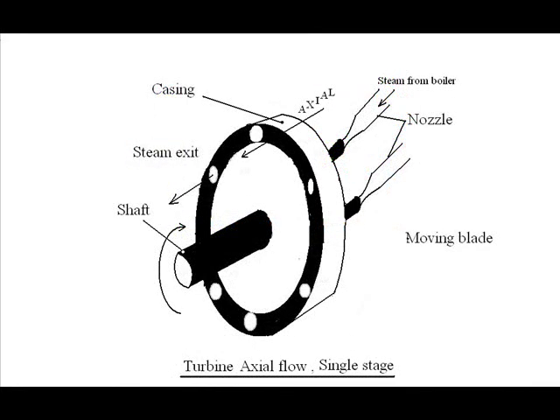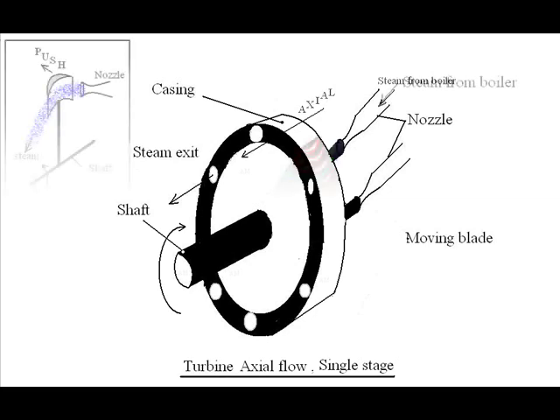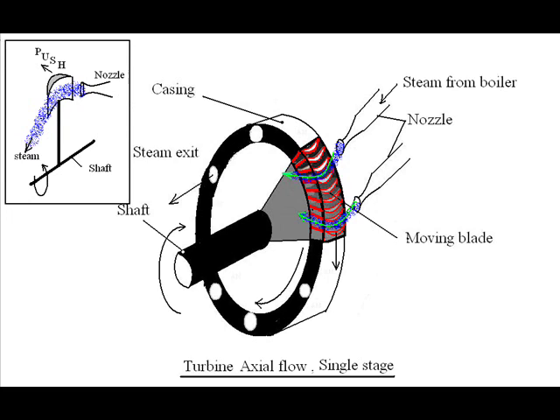The axial-flow steam turbine has three basic components: the casing, the shaft, and the nozzles. In axial flow, after exiting the nozzle, steam flows over the turbine blades in a direction parallel to the axis of rotation of the shaft — this is why it is called an axial-flow turbine. In the cut section, we can see steam shown in blue coming out of the nozzle and gliding over the blades, which get a push in the tangential direction.